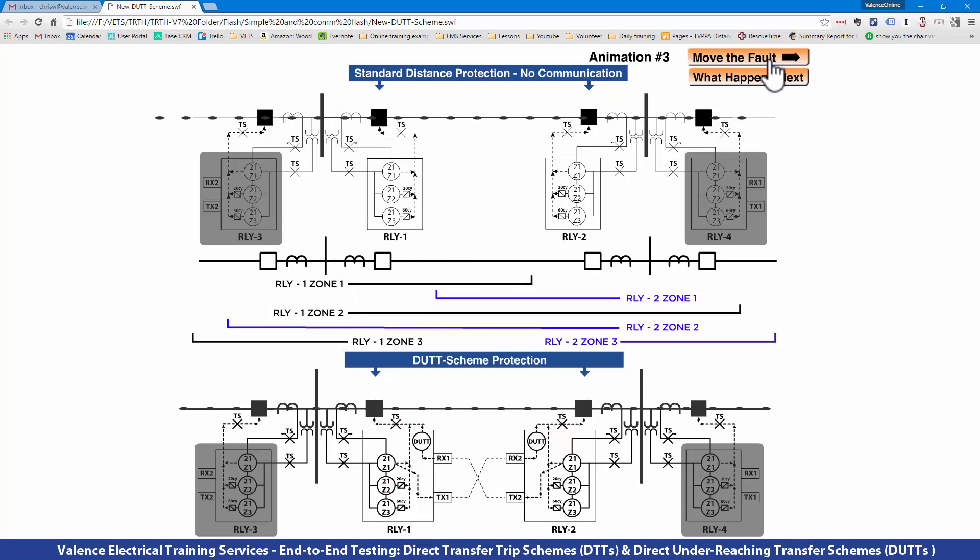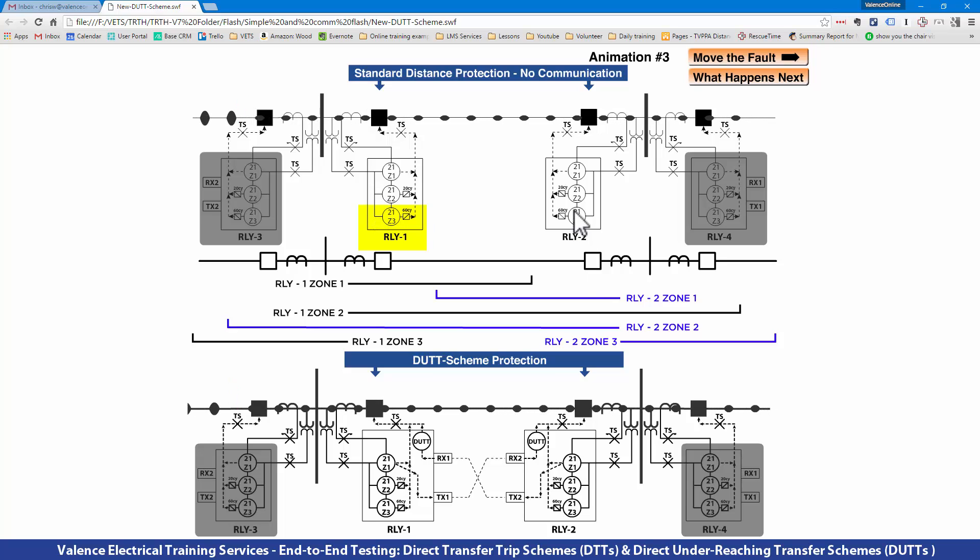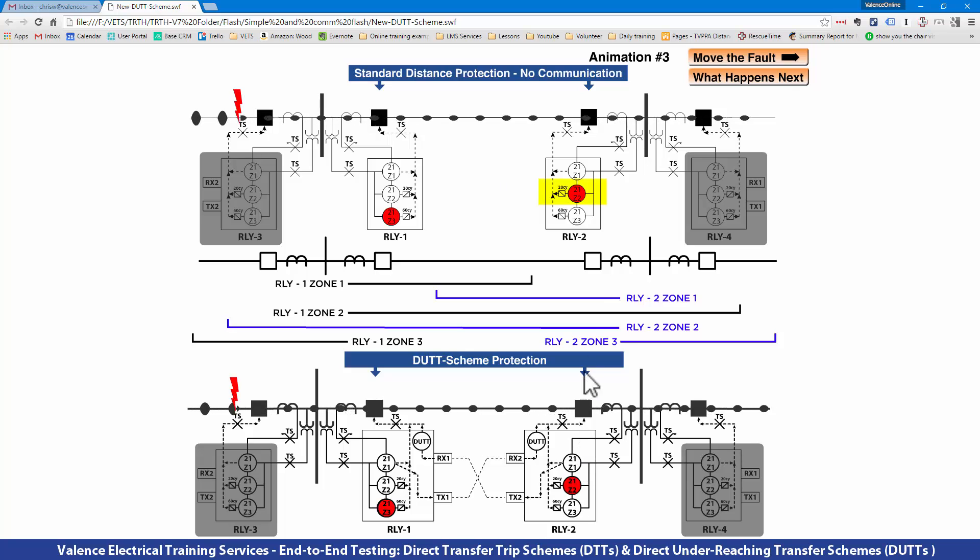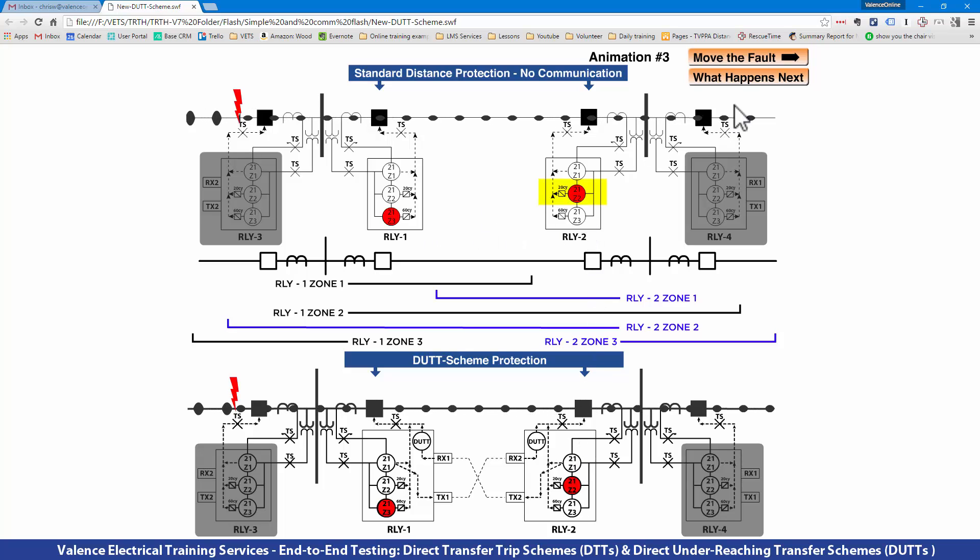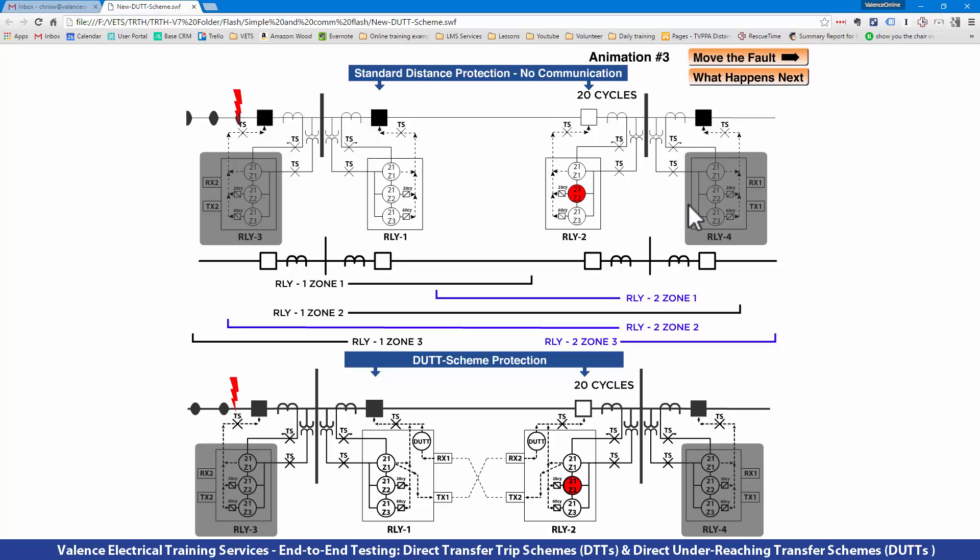If I go outside of the zone, this relay sees Zone 3 and Relay 2 sees Zone 2. Zone 2 has a faster time delay than Zone 3, so the Zone 2s operate in the same amount of time. The DUTT scheme gives us the benefit of saving 17 cycles for faults on the line while giving us our normal backup protection for faults outside of the line.